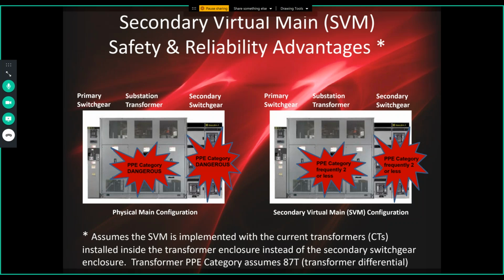So here on the left, physical secondary main, we have PPE category dangerous inside the transformer, and PPE category dangerous inside the switchgear. So we have an inherently dangerous situation with respect to personnel safety, as well as danger to the equipment itself. The equipment can and usually is catastrophically damaged beyond the ability for field repair in these arc flash incidents.